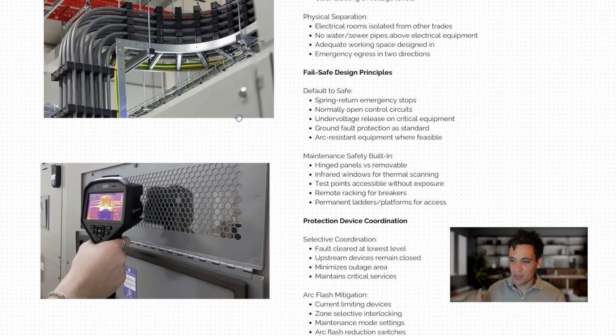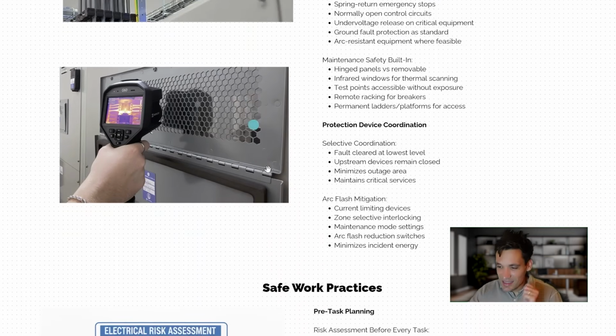Remember we spoke about with arc flash that the longer you have a fault, the worse the arc flash is. So you want to clear your faults fast enough that the arc flash level's safe to walk around and operate in. So if you have a worker standing in front of a main switchboard and there's a fault, you don't get some huge arc flash that puts them at risk. So that's the design side.